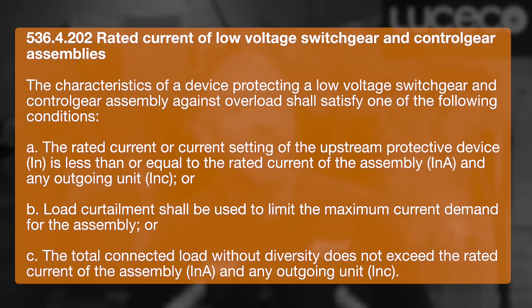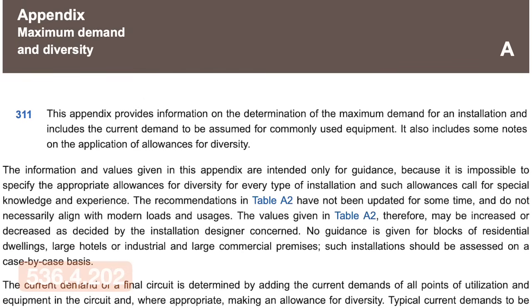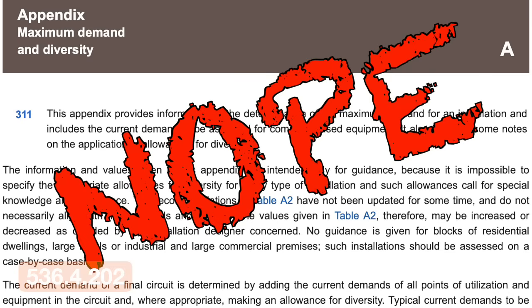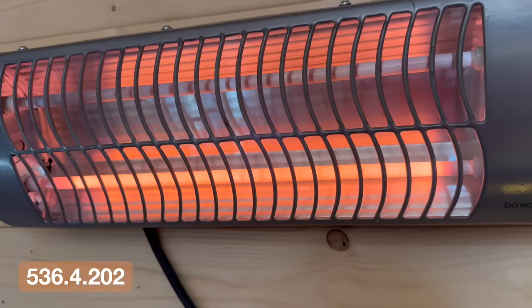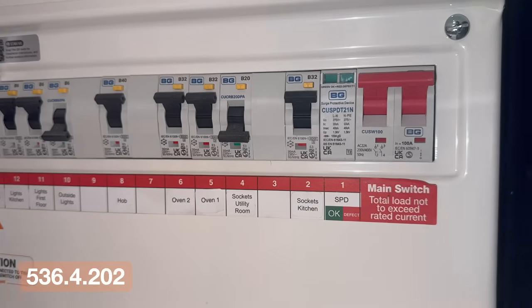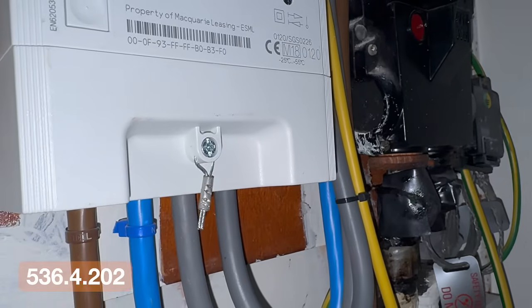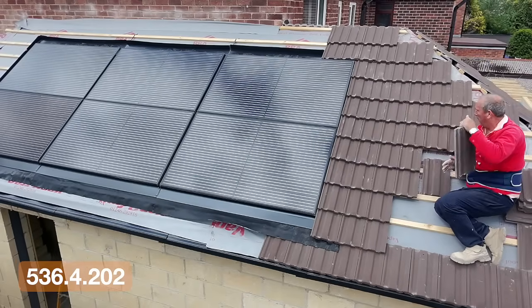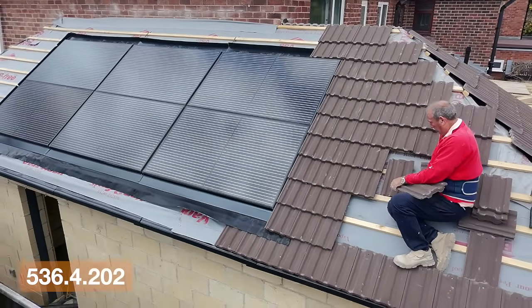And this is where things tighten up. You are not allowed to rely on diversity here. Nope. You have to assume the worst case scenario. Everything on, everything contributing. So if you had a 100 amp board and 60 amps coming from the grid and another 60 amps coming from the battery or a PV system, individually that may look fine, but together that exceeds what the assembly is designed to handle.